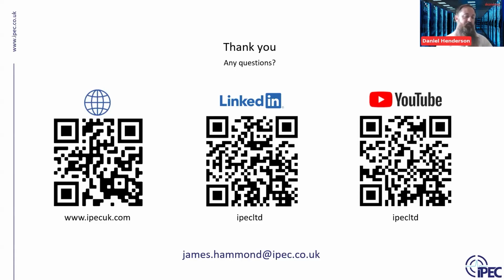I had a couple of examples in Indianapolis, at a site out there where their maintenance frequency was, I think, 5 years for the assets they were maintaining - pad mounted transformers, things like that. Within that, I think at year 3 they started doing these PD assessments, and two bits of that equipment were getting high levels of partial discharge. So they planned the downtime in, took it down in a planned way, and that was it. The whole environment around there had changed conditions - from what it was like before to what it was like after - and they'd been getting an increase in debris from adjacent roadways, where they'd changed the nature of the traffic, things like that. You could see the tracking where it was. So I'm a big advocate for PD testing.